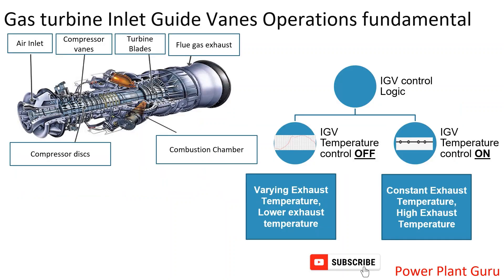In this section we will discuss the majority of operational concepts. For any gas turbine operator or user, IGV control logic is divided into two parts: one is IGV temperature control mode ON, and the other is temperature control mode OFF.